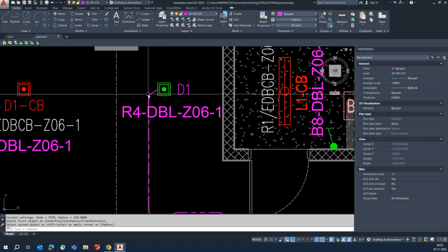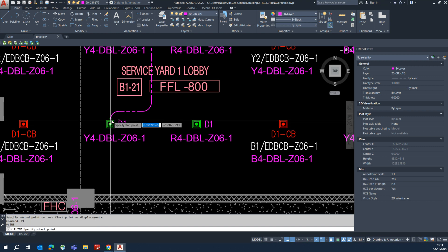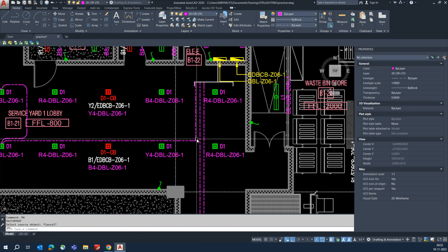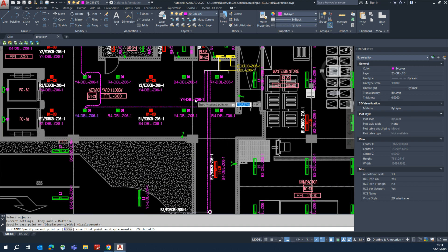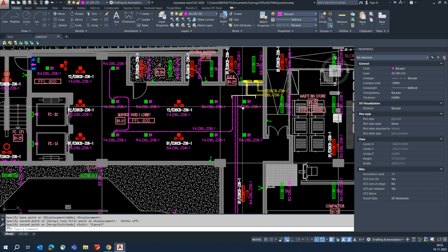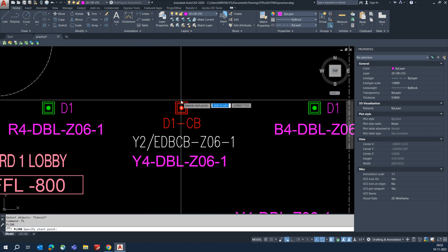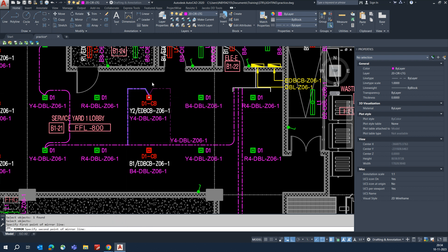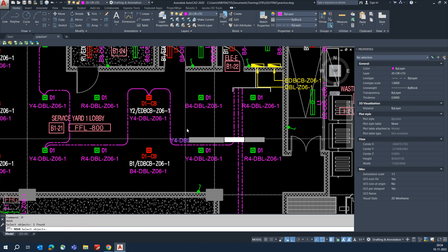Beautifully arrange the lighting circuits like that. If you want a different color, you can change it. Connect this line to the DB, give a fillet, and add the circuit number Y4 here. This means the Y4 circuit is going this way. This is an emergency light, so you need to connect it to both normal power and emergency power. Trim and fillet as needed.